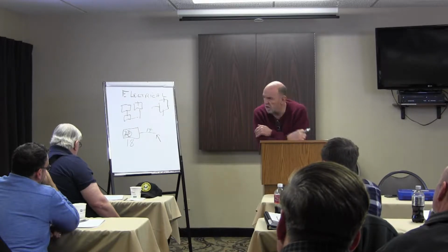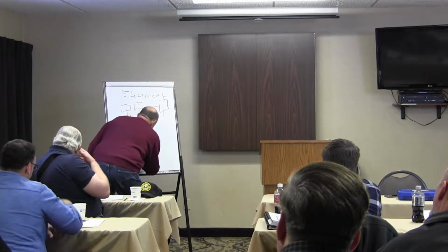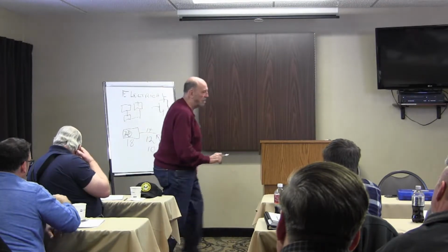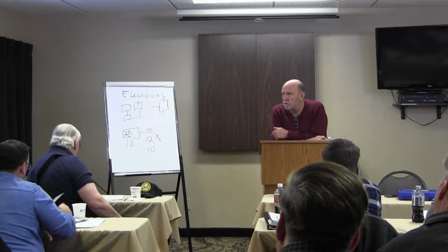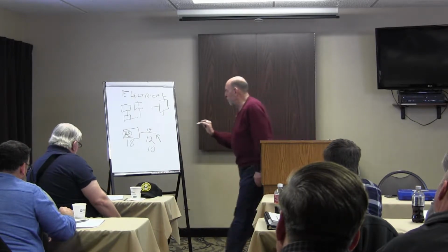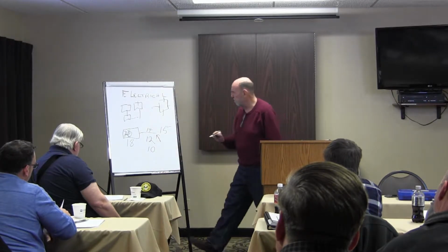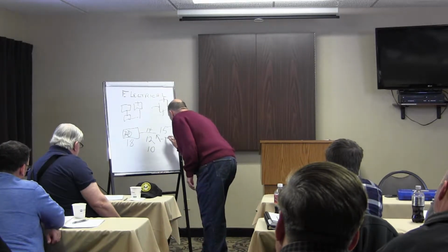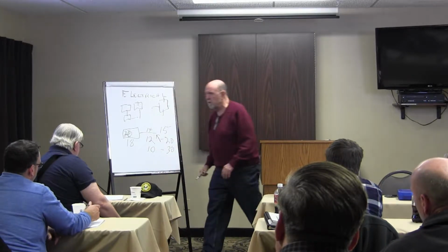To protect those wires, we have 14 gauge wires, we have 12 gauge wires, we have 10 gauge wires, which are the three most commonly used wires throughout the house. And this 14 gauge wire can handle 15, it's rated for 15. This 12 gauge is rated for 20, and this 10 gauge is rated for 30.